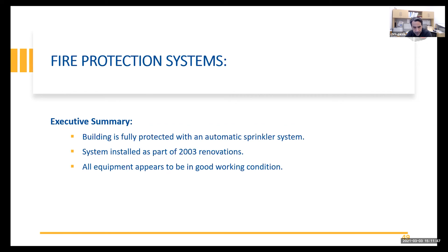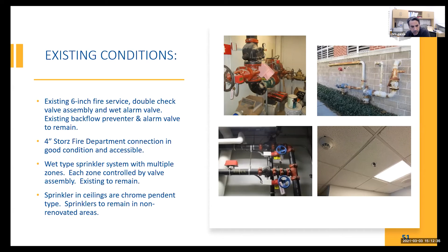Existing conditions, there's a 6-inch fire service with backflow preventer and alarm valve that is located in the mechanical room on the mid-level. There's a 4-inch fire department connection on the outside of the building adjacent to the gas meter. It seemed to be accessible, and wasn't damaged in any way. The building has multiple sprinkler zones. All of the zones are controlled by their own dedicated shutoff valve, and each zone has a flow switch, all monitored by the fire alarm system. And as I said, the sprinklers are provided throughout all the spaces within the building.